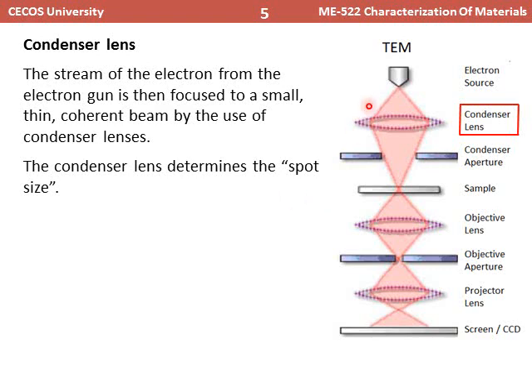The next part is the condenser lens. The stream of electrons from the electron gun is focused to a small, thin, coherent beam using the condenser lens, which is an electromagnetic lens. The condenser lens determines and controls the spot size, which is very similar to its function in scanning electron microscopy.